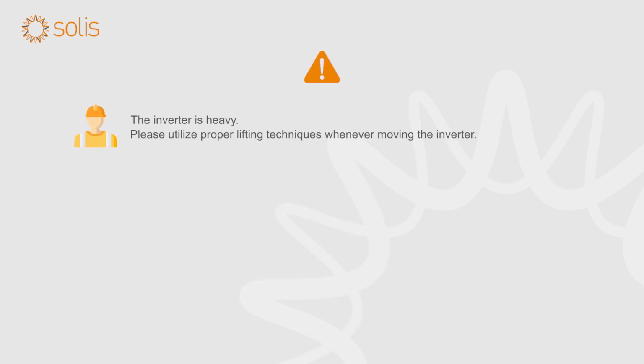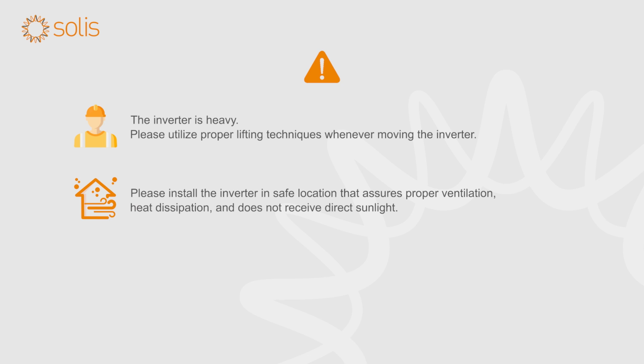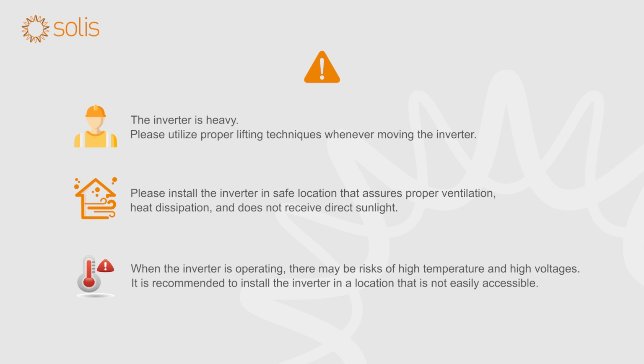The inverter is heavy. Please utilize proper lifting techniques whenever moving the inverter. Please install the inverter in a safe location that meets the requirements for proper ventilation for heat dissipation and avoidance of direct sunlight. When the inverter is operating, there may be risks of high temperature and high voltages. It is recommended to install the inverter in a location that is not easily accessible.